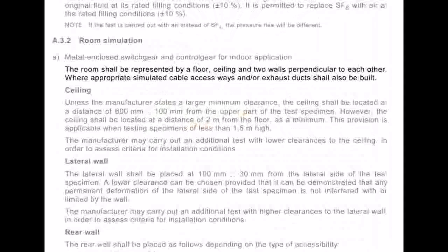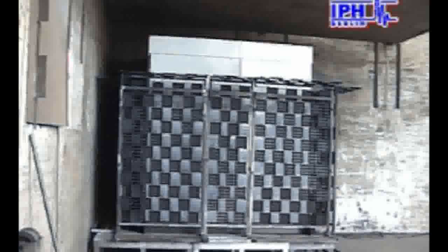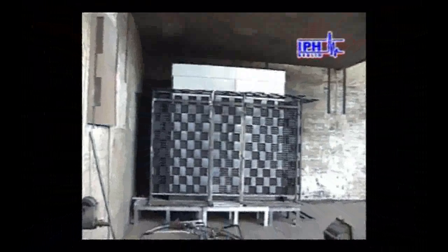Thus, the new IEC demands that a room be simulated for testing the internal arc effects. This means erection of side walls, rear walls, and a roof to be erected, and then the medium voltage switchgear is to be placed in this built-up, and then it has to be tested.